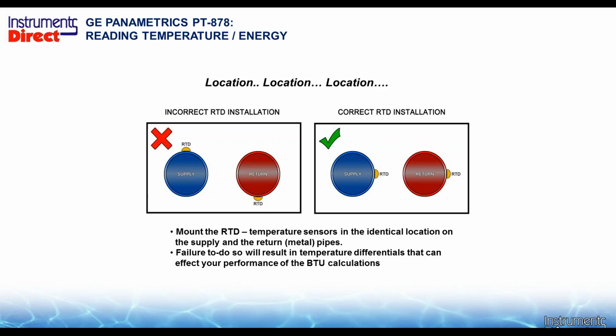And in doing that, you need to install the temperature sensors on the pipe correctly. In this case, if I were to put one on the supply and one on the return line, one at 6 o'clock and one at 12 o'clock, the heat would rise here, and I could have a couple of degrees of temperature error on this application.